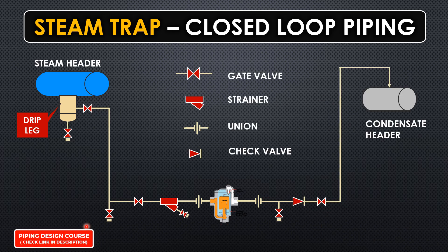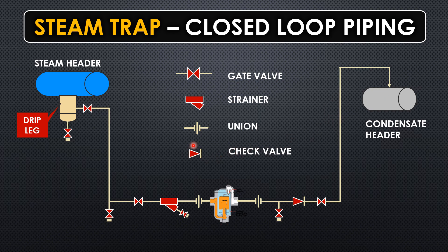Now let's go to the closed loop system. In a closed loop system, the line goes back to the condensate header rather than the trench. There is an additional component — a check valve — installed before the isolation valve. This is to protect against backflow: if there is no check valve, condensate could flow back. The check valve prevents flow from the opposite direction. The closed loop also requires a drip leg, strainer, unions on both sides of the steam trap, drains, and isolation valves.